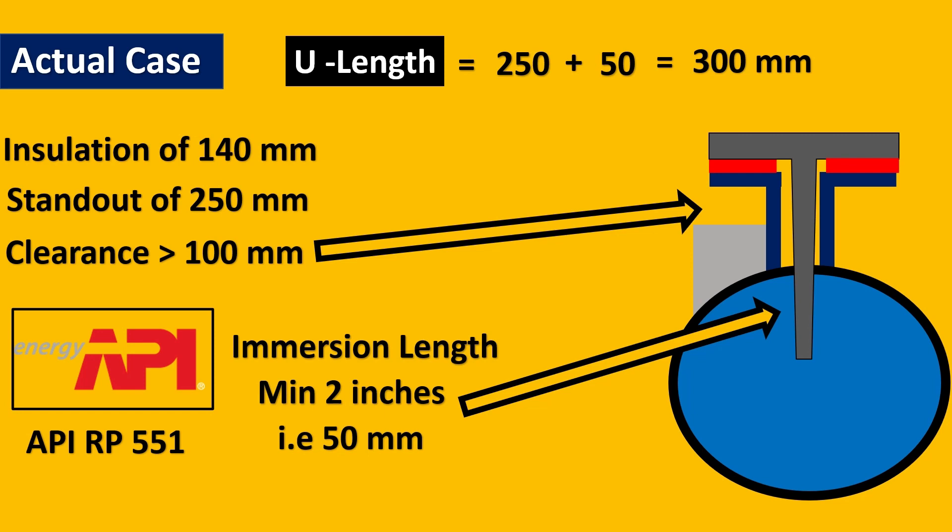So this is how you can use in Excel once you are clear with the concept and calculate U-length for all the thermowells that have to be used in the plant. And then remember one thing: they have to go through the wake frequency calculations and maybe the length or the tip thickness would get modified for a very few cases. But majority of them usually pass.